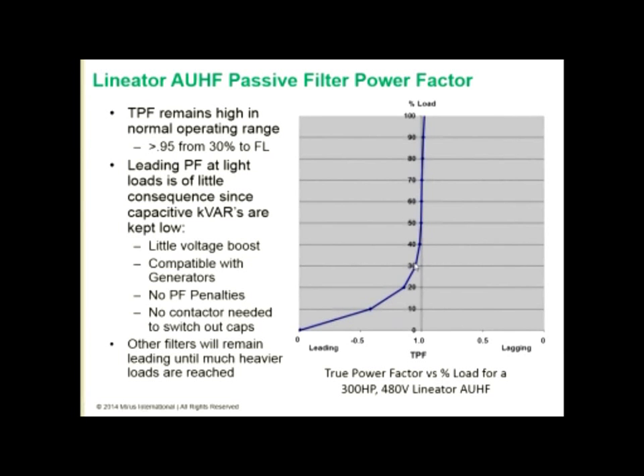We do end up approaching a leading power factor, and that will drop off and go down to 0, because at no load, essentially what we have is just the capacitors of the filter connected to the system. So we'll have 0 leading power factor. So the power factor can be low and leading with the filter under light loading conditions, but that's not a problem because the filter introduces very little voltage boost and it's compatible with the generators. It won't impact power factor penalties because remember we're lightly loaded when we go leading, and therefore there is no requirement to switch out the capacitors with a contactor. Other filters, of course, will remain leading until much heavier loads are reached and therefore can introduce problems to the generators.